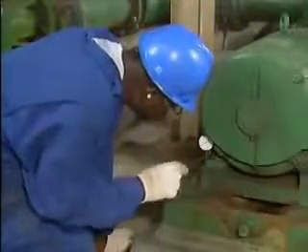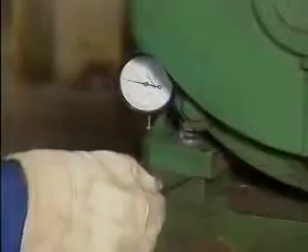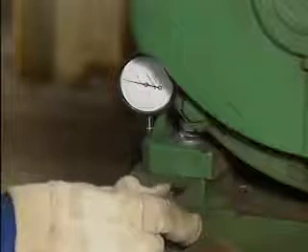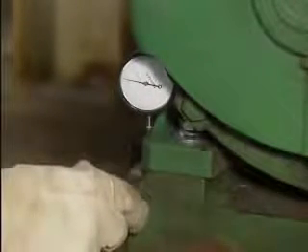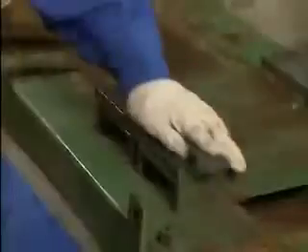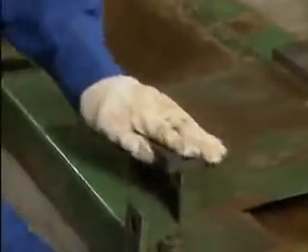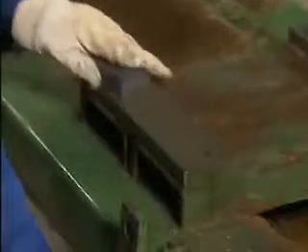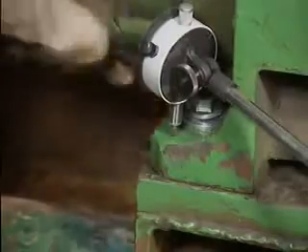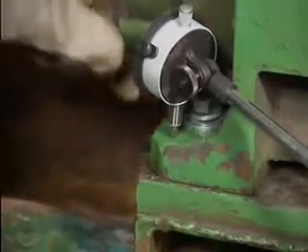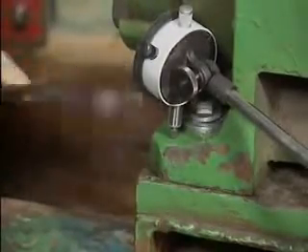Each foot of the motor should be checked in the same manner. Now, if a soft foot is detected and the feeler gauge won't slide evenly under the foot, then the foot may not be parallel to the base. In that case, the foot or the seating surface of the foundation may have to be reworked, or the foot may require special shimming. In any case, once corrections have been made, the procedure should always be repeated to verify that the soft foot condition has been eliminated.